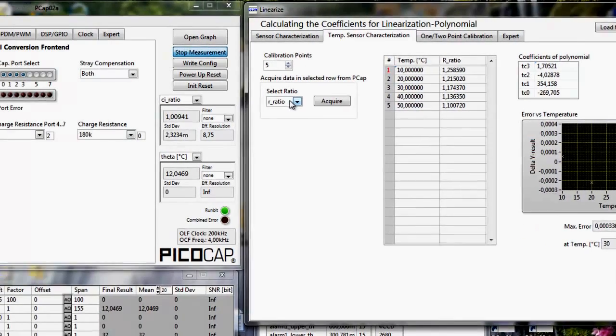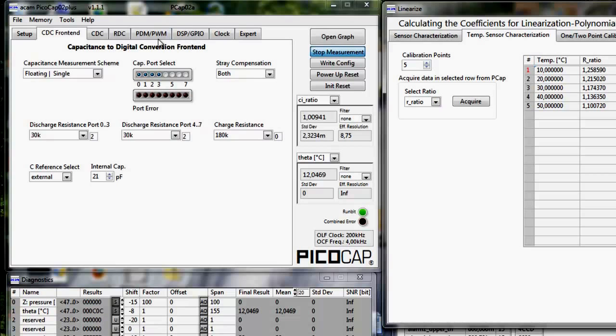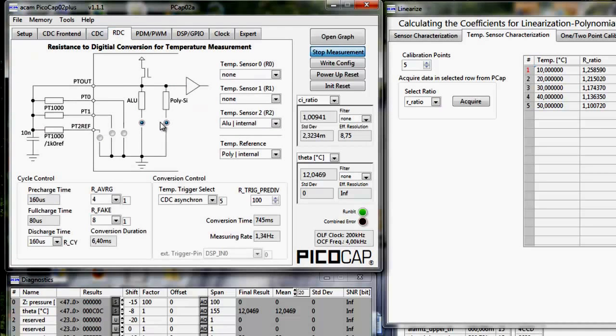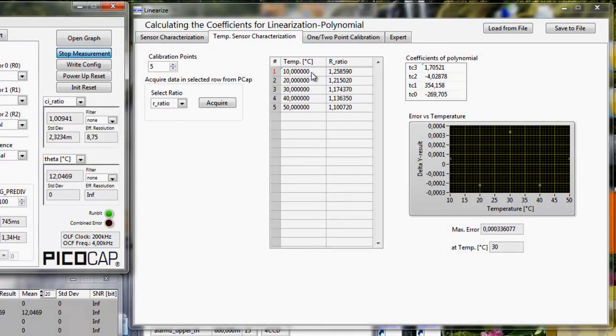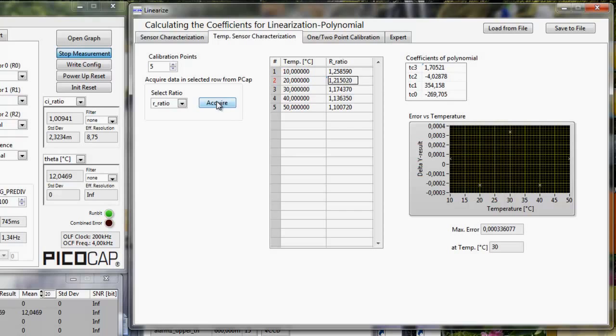So we selected previously the RDC to be the internal one, so the aluminum temperature sensor, and having also the internal polysilicium reference. So here you can set several temperatures, like from 10 to 50 in this example, and by clicking in the corresponding line and saying acquire, also the ratio will be acquired. And you see that by this also the coefficients of a polynomial are calculated here automatically. So this way you can characterize your temperature sensor.